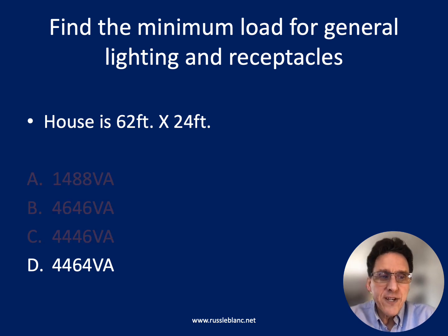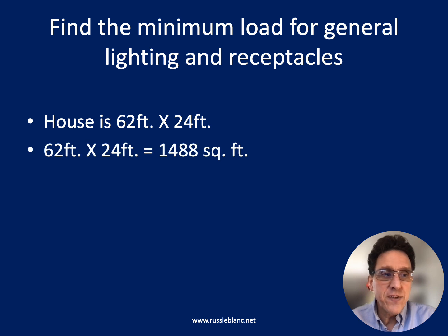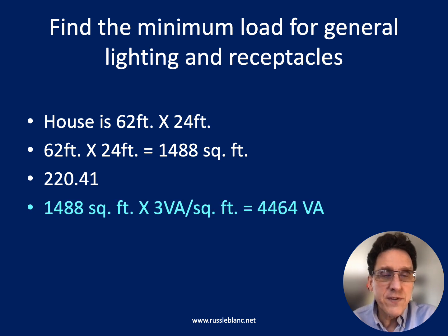So the correct answer here is 4464 VA. Now, how do we get to that point? We just take this square footage, 62 times 24 equals 1488 square feet. That's the square footage. And according to 220.41, we need to now multiply that by the unit load of 3 volt amps per square foot. And so there's that math. And that works out to the 4464 VA.